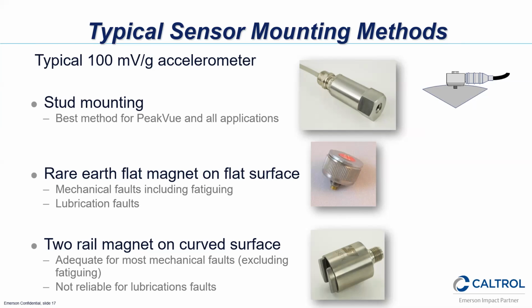But on air handlers where we can't access, or cooling towers where we can't safely access the fan bearings or the motor bearings, we'll permanently mount low-cost accelerometers right onto the bearings, and then we run them out to a junction box where we can collect safely on the outside. This is usually one of the deterring costs of getting a program started, because unfortunately there are a lot of air handlers that are not accessible, and there's a bit of a cost up front to outfit those air handlers so we can collect the data on them.